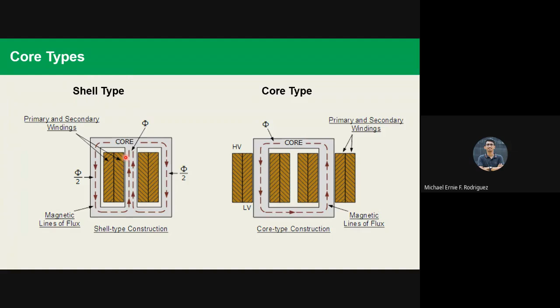What's the effect of that? It provides a better magnetic circuit, but the units tend to become larger and heavier, so the shell type is heavier. This type is usually restricted to the larger size transformers found in substations and underground network units, and they are usually three-phase units.